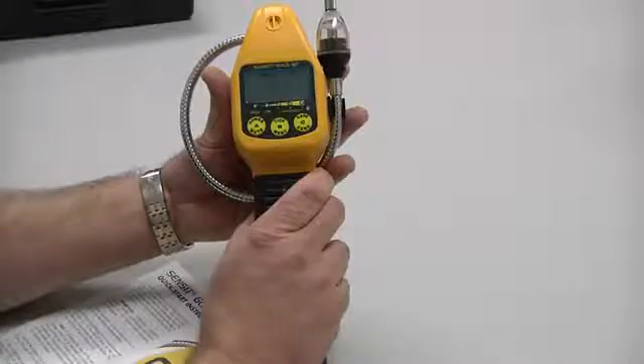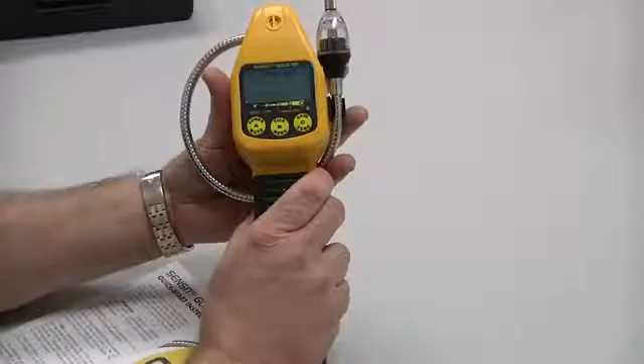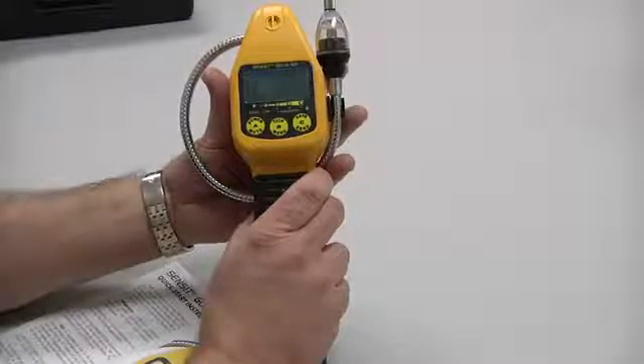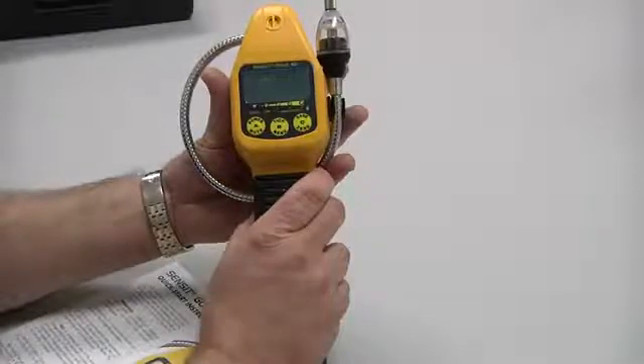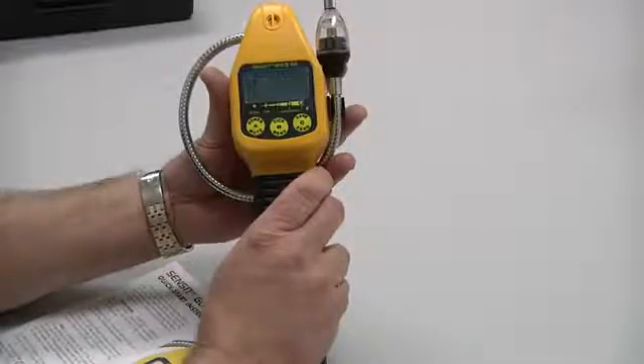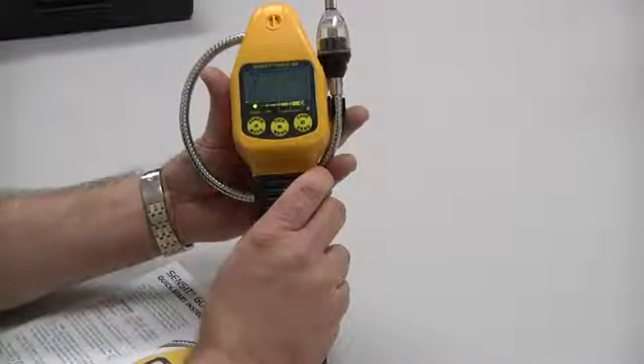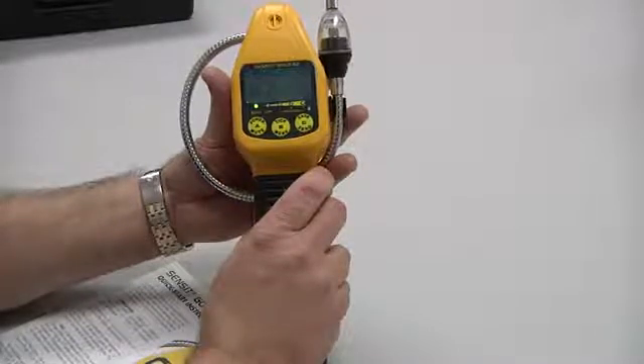During that warm-up, it does indicate when the calibration will be due for the next calibration. Next is an auto zero in which all of the sensors are analyzed for being in a proper zeroing and now we have a full working display.